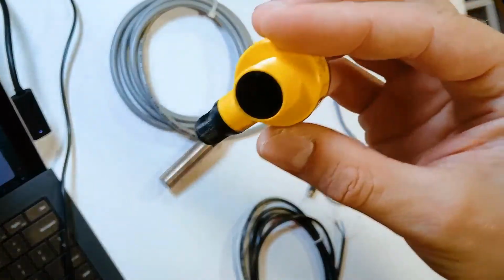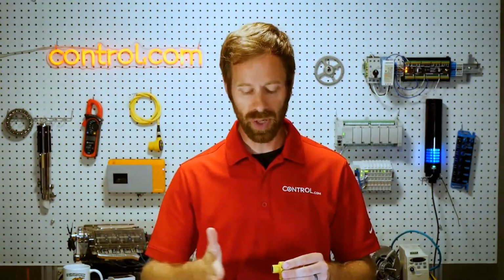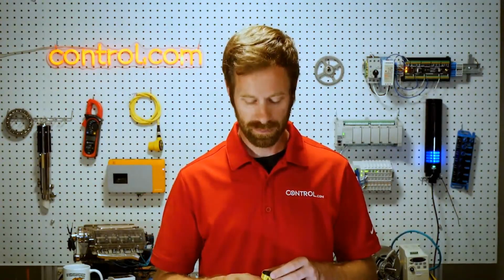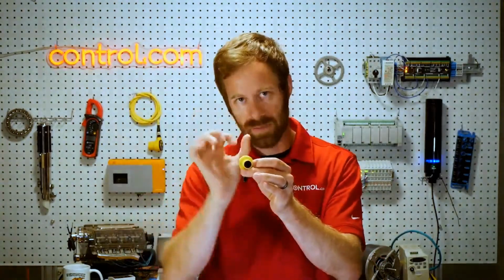Another sensor, this one is another optical sensor from a different manufacturer. It also has four wires, but in this case the fourth wire is used to send a couple of pulses to teach the sensor what is an acceptable range or window of operation for the object that's coming into its field of view. Some sensors have buttons or potentiometers that we can adjust, but it's great to be able to install our sensor, and if something needs to be changed, we don't have to walk up and push on the back of the sensor or find a screwdriver and change it. We can simply send a signal remotely. So there's a lot of different uses of that fourth wire depending on the datasheet's value.